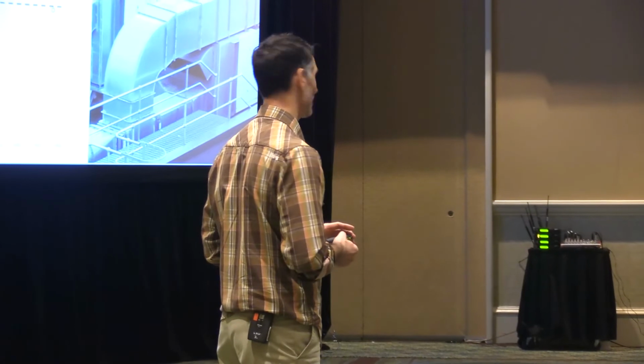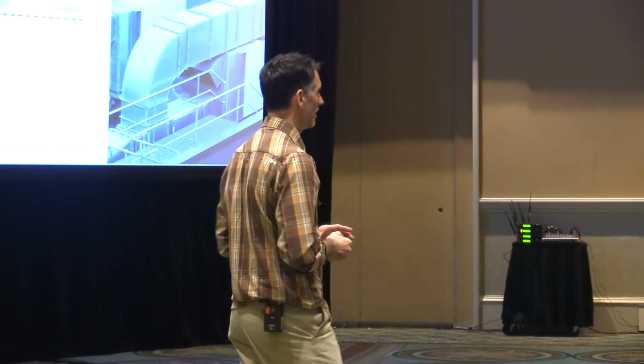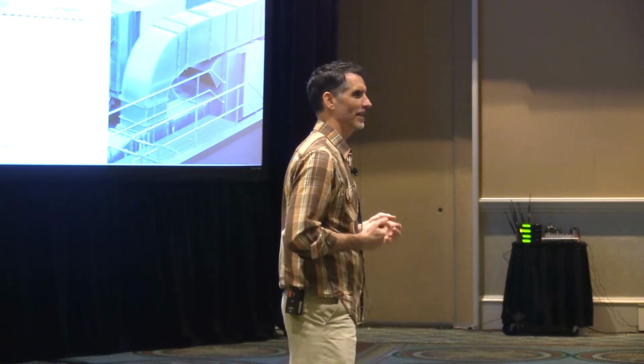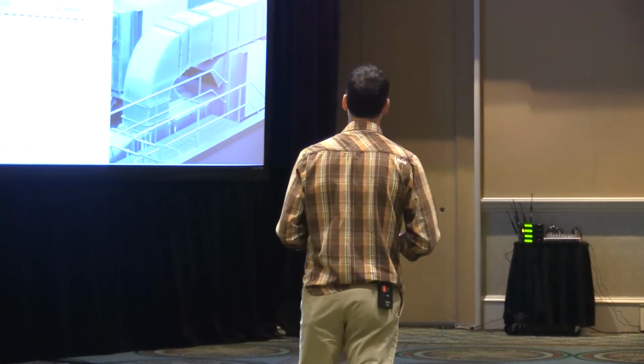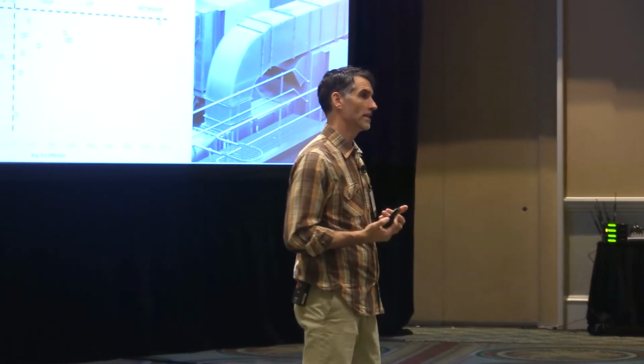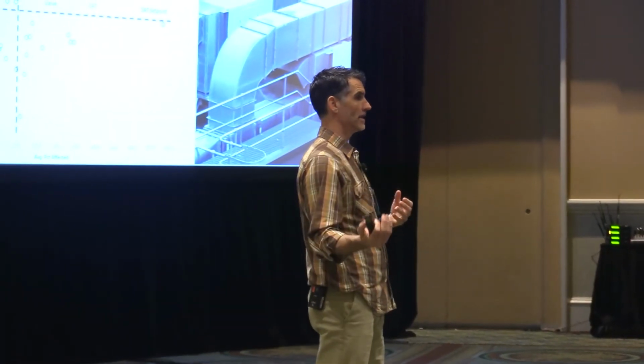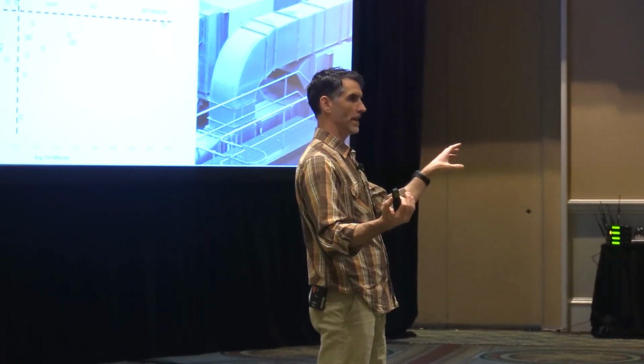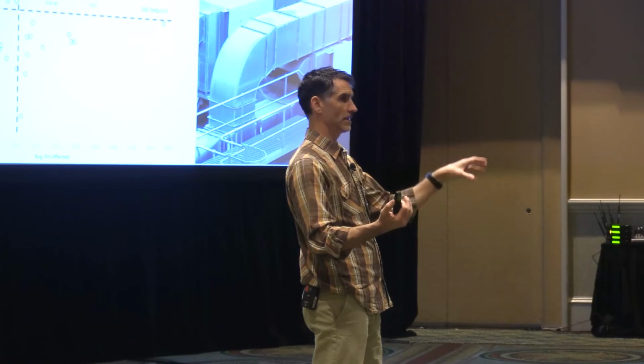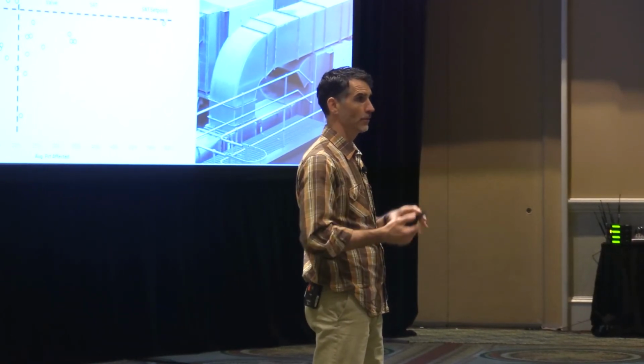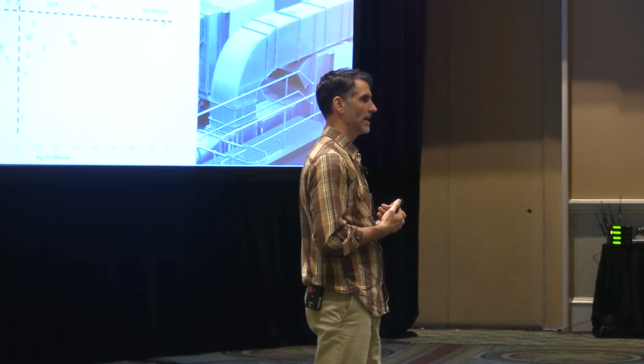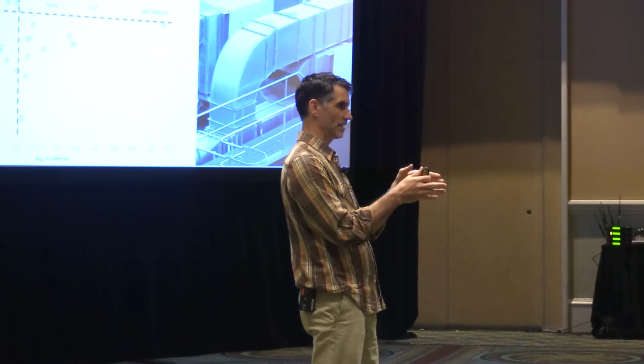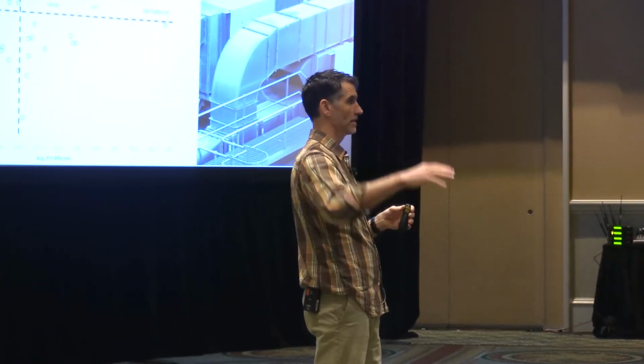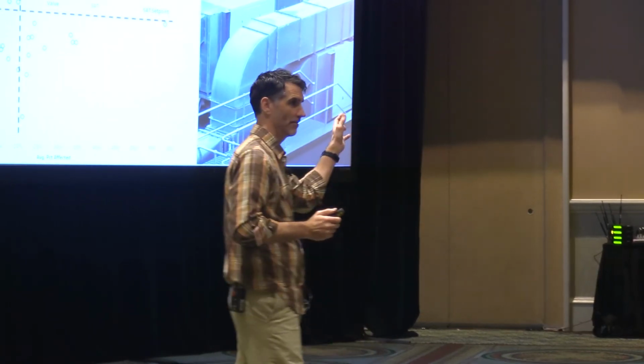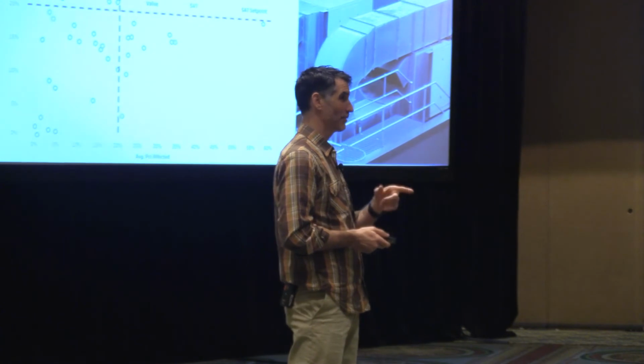That's a good question. When I saw the results, I had the same thought. Obviously, you can't just say the outside air temperature sensor is faulty. But some tools will look at more logic-based rules, like cross-checking an outdoor air temperature sensor against a local weather station, or against another sensor in another building on the campus. So it's looking at a mismatch that it can't necessarily pin to one sensor being wrong. It's just saying something doesn't look right here. It could be this sensor, it could be the one we're comparing against, or the weather station could have something funky going on.